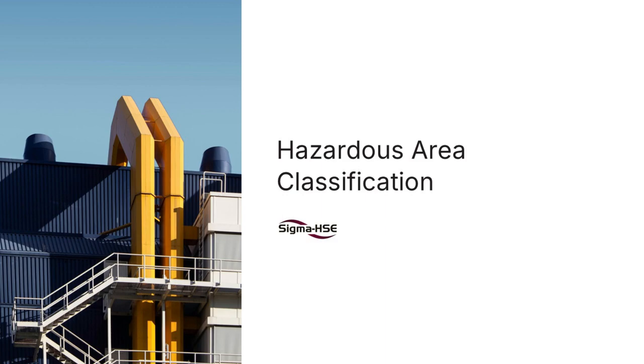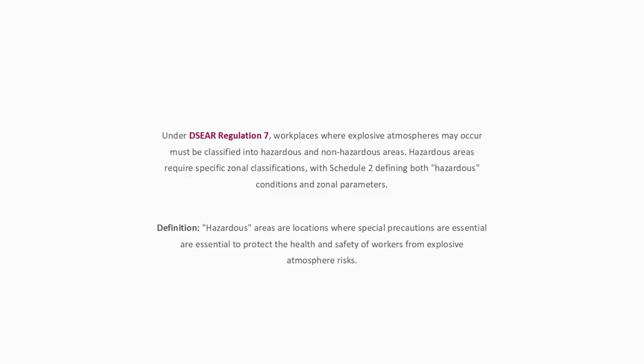One of the things I spoke about earlier was hazardous area classification. How often will the material be present and how far out will it come? DSEAR Regulation 7 says places where explosive atmospheres may occur are classified into hazardous and non-hazardous areas. Hazardous areas must be given zonal classification, and Schedule 2 gives the definition of hazardous and the zonal definition.